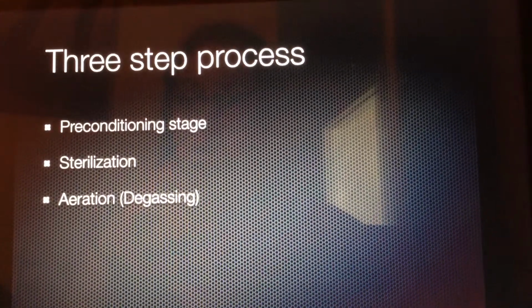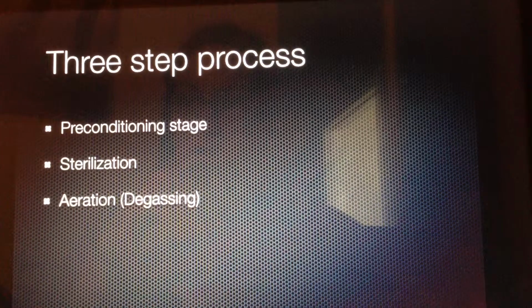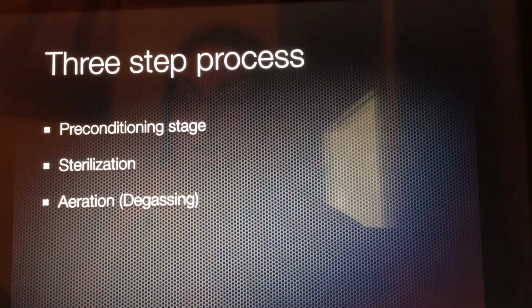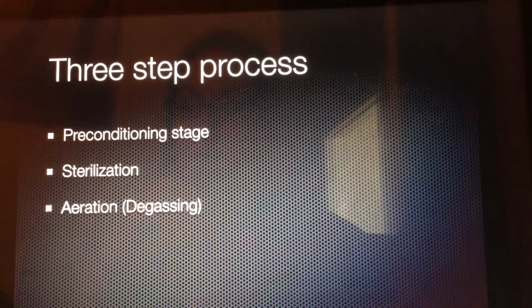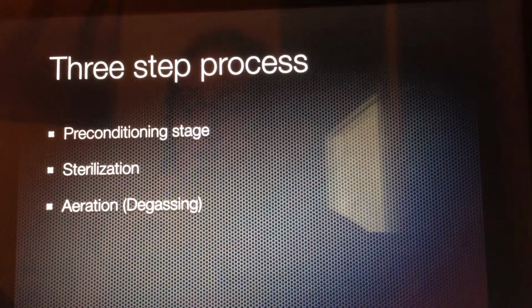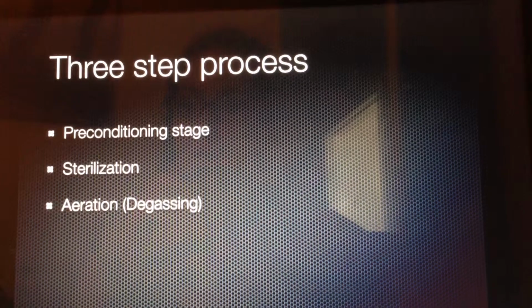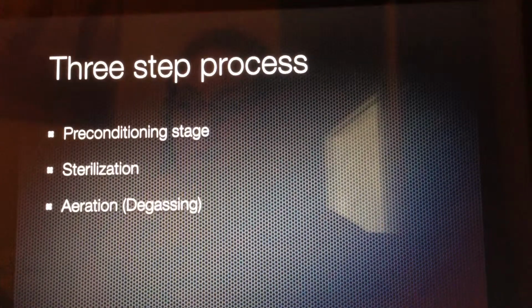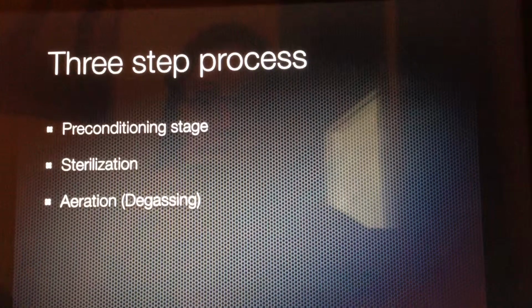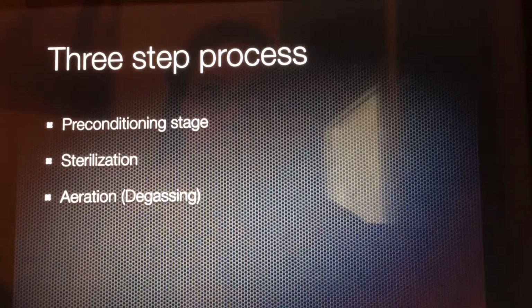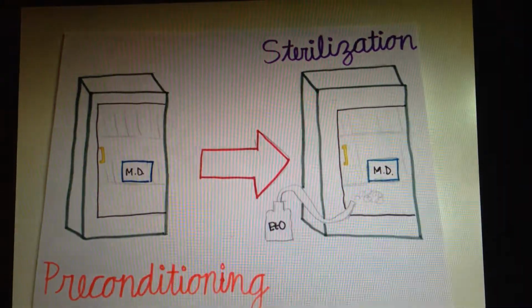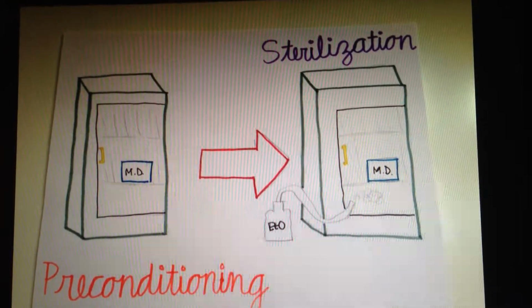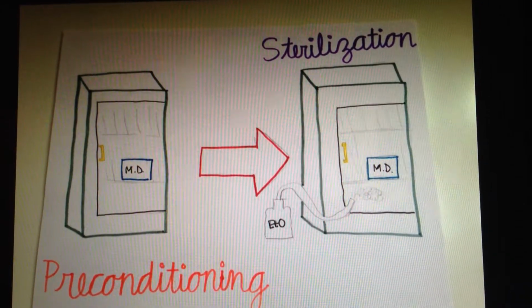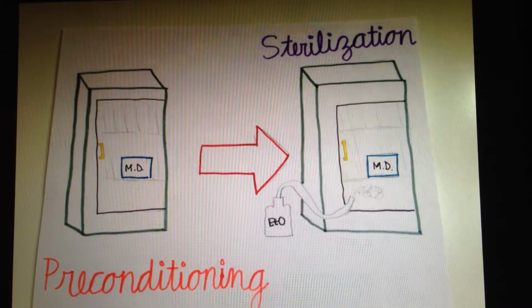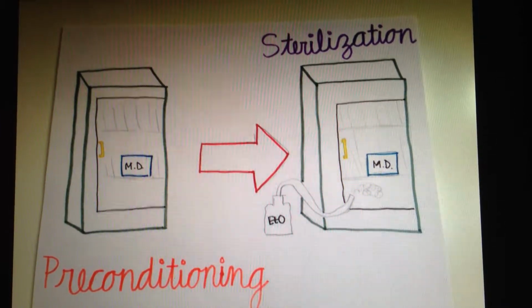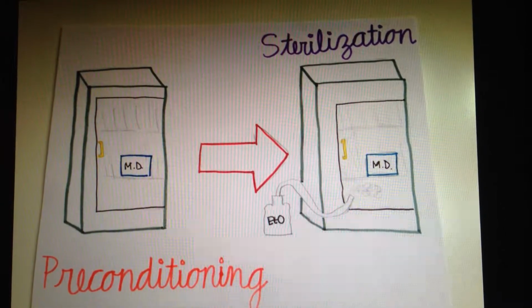In the sterilizing step, there is an initial vacuum to draw out the ambient atmosphere, and then humidification happens in the chamber. The ethylene oxide gas is then injected into the system, and the packages will have a dwell time. It is known that the package does need to have a good permeation, since the ethylene oxide gas will permeate through the package to the product to make sure that the microorganism has been killed.